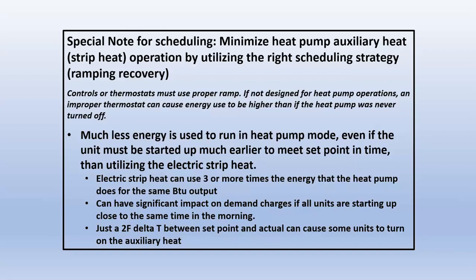Especially in states like where I'm at in South Carolina, some of the warmer states where heat pumps are more prevalent, the schools were getting murdered by this, especially on demand charges, because every one of these would pop on at the same time, and they thought they were saving money. They turned everything off at night without thinking about it being a heat pump. And then they'd get that boom. All those 10 kW auxiliary heaters would pop on at the same time and just murder their demand. So there's things you've got to do around that.